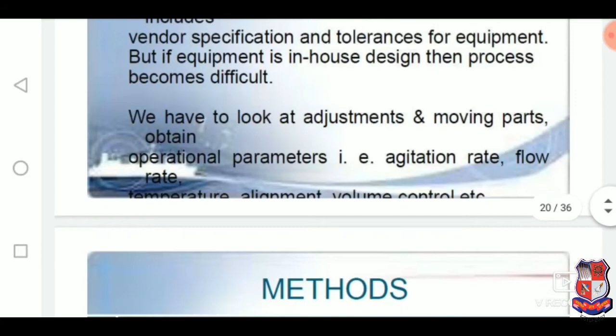So the first one is calibration. Non-compendial and some compendial apparatus do not have calibrated tablets. In some cases, in-house calibrated tablets are designed. Some unique aspects of equipment can only be detected with USP calibrated tablets, as there are no practical measuring tools available for analysis, for example, vibrations and vessel irregularities. So, USP calibrated tablets, for example, prednisone tablets, are generally used for calibration purposes.